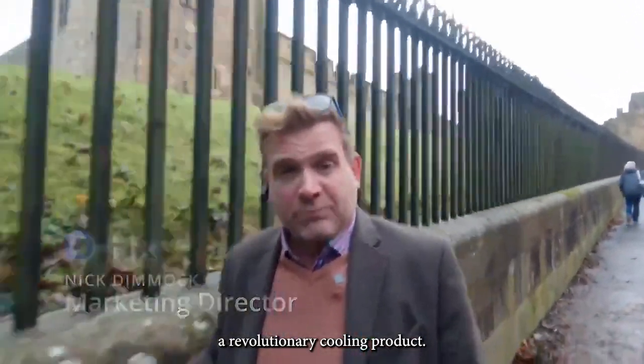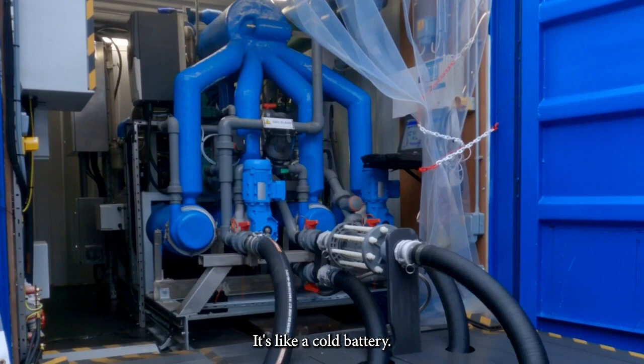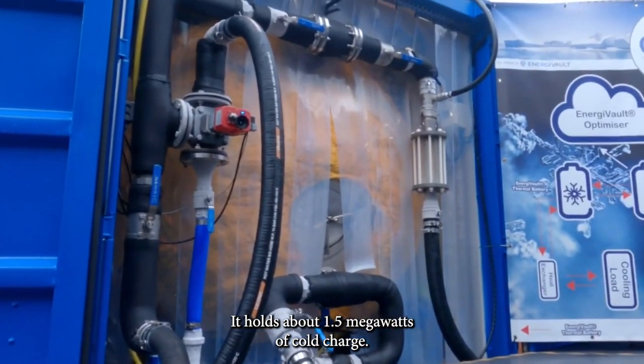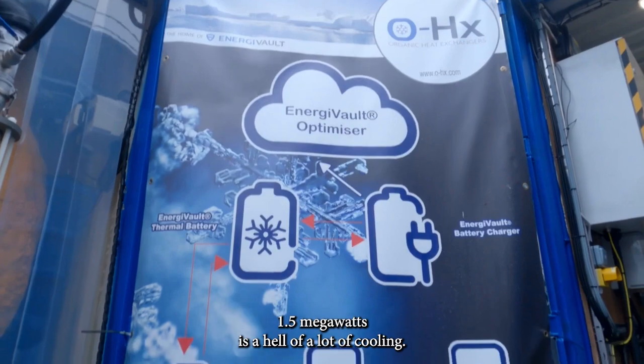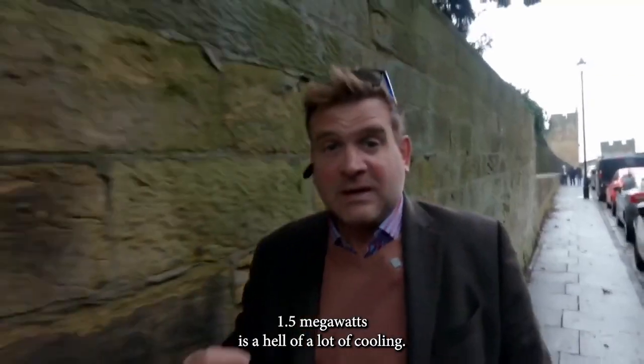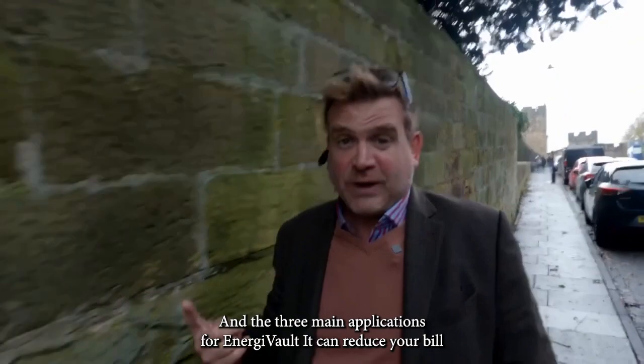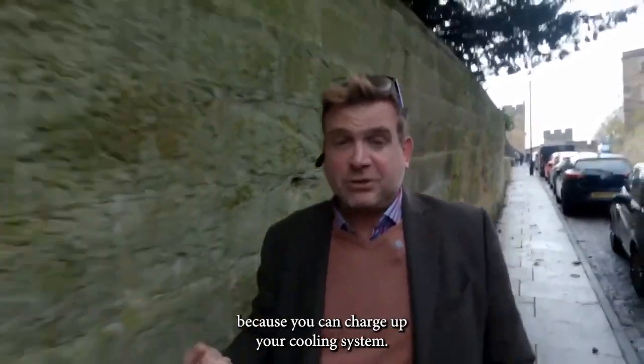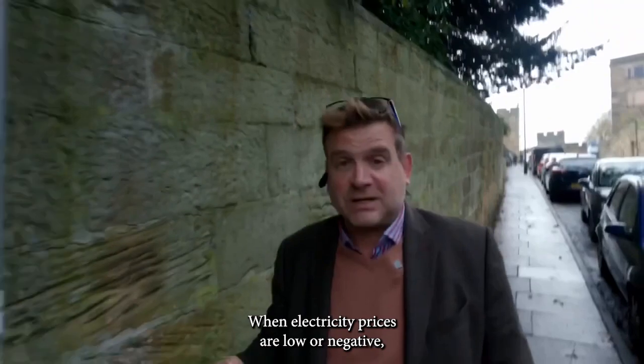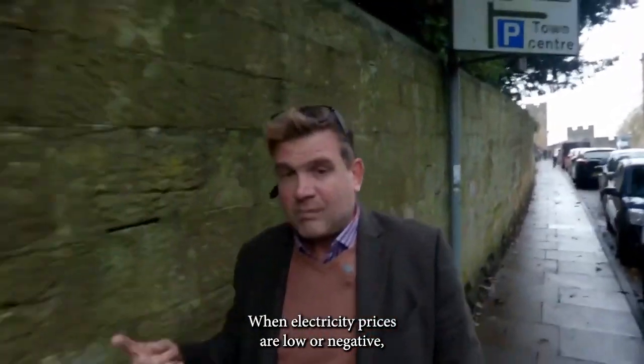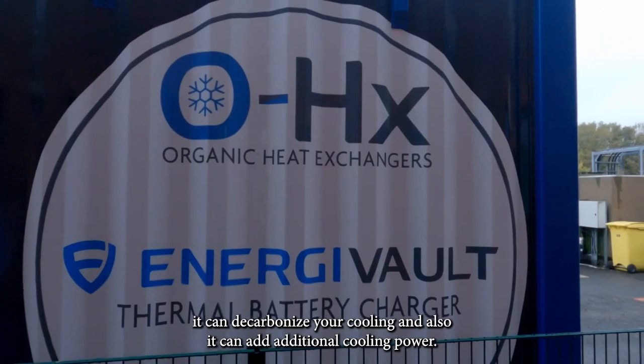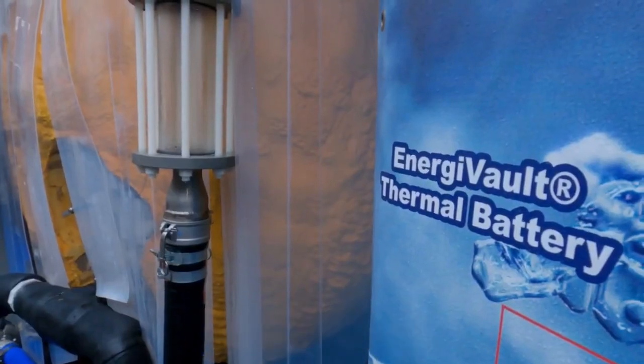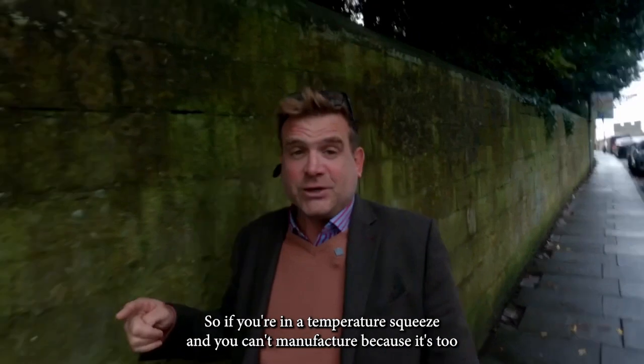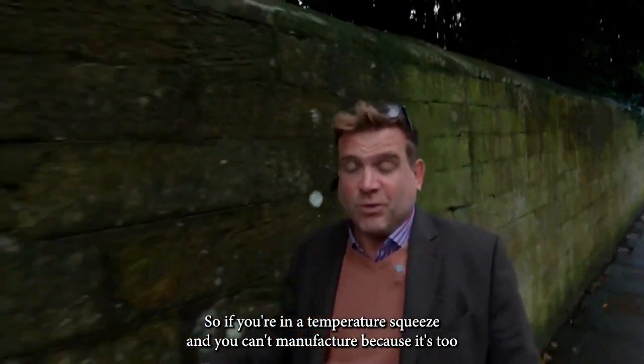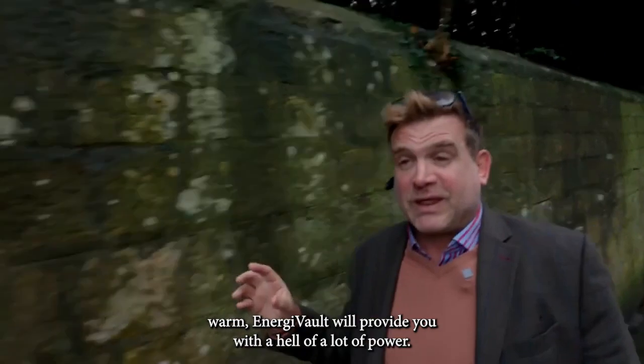EnergiVault is a revolutionary cooling product. It's like a cold battery, holding about 1.5 megawatts of cold charge. That's a hell of a lot of cooling, and there are three main applications. It can reduce your bill by charging up your cooling system when electricity prices are low or negative, it can decarbonize your cooling, and it can add additional cooling power. So if you're in a temperature squeeze and can't manufacture because it's too warm, EnergiVault will provide you with a hell of a lot of power.